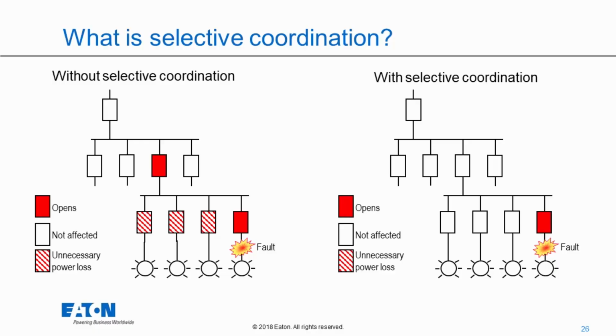If we do not have selective coordination, the overcurrent device nearest the fault is not able to clear before the opening of the upstream device. And what happens then is when that upstream device opens, I lose power to unfaulted loads. And so the real reason why we have selective coordination is where we have the need for enhanced system reliability. That really is what drives the requirements where we have selective coordination. And there are several areas of code we'll talk about where we have requirements for selective coordination, but basically we're talking about critical systems.